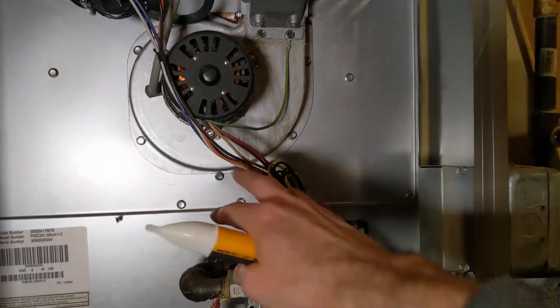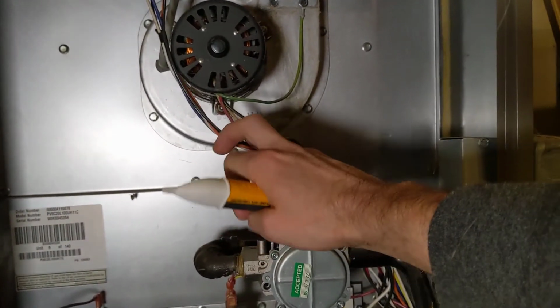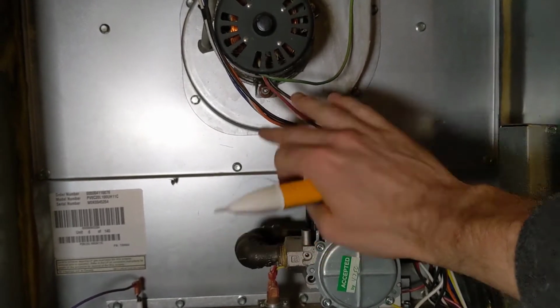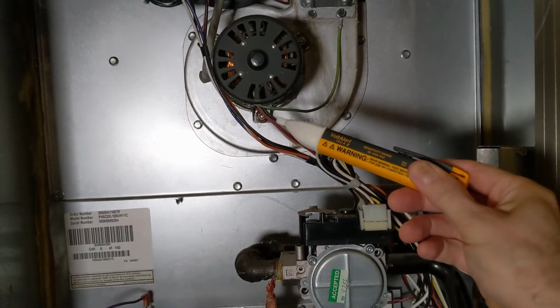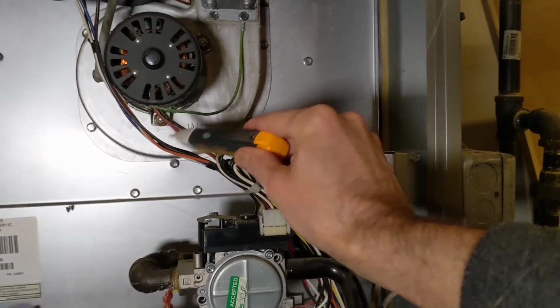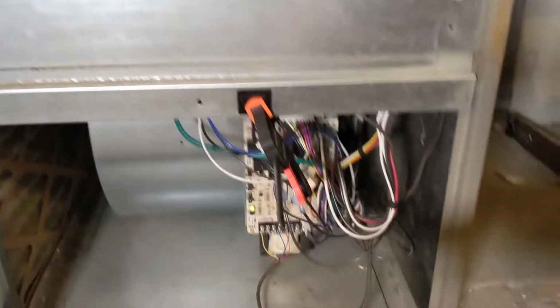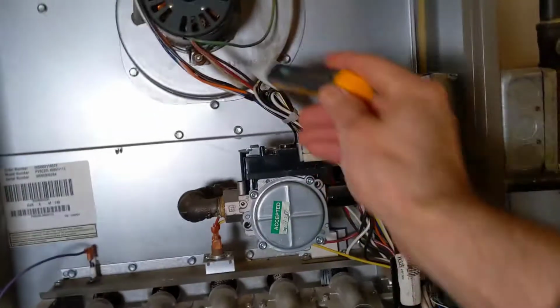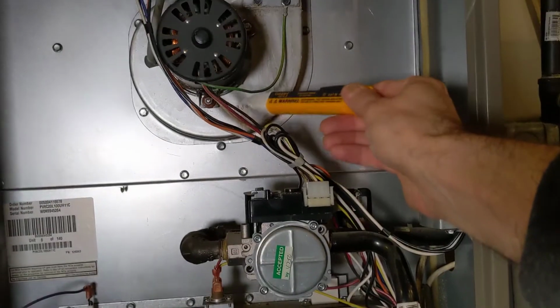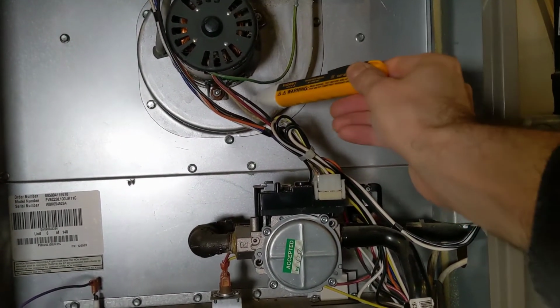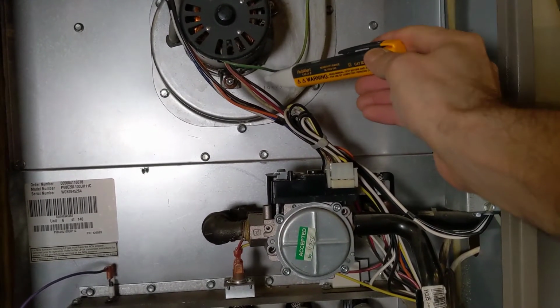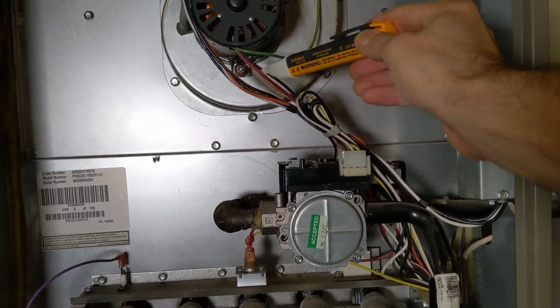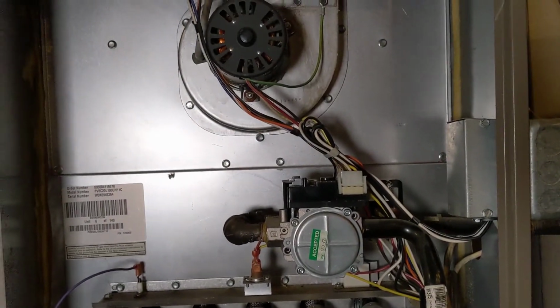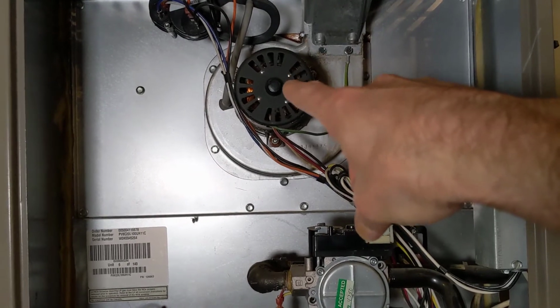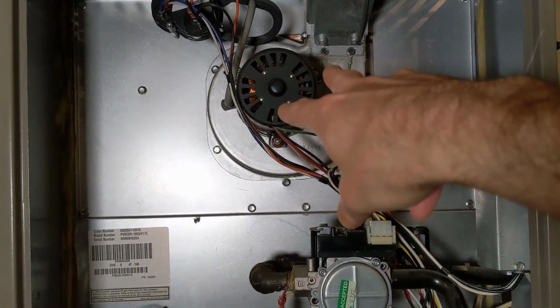The way you can maybe make a determination of that is this motor has some wires coming into it, usually like a red, white, or red, white, and black. What I would do is take my non-contact voltage tester and see if there's any power going to these wires. If everything is lit up and it's calling for heat, you should have full line voltage, meaning 110 volts. That's typically what this motor runs at. So if you touch the black or red wire, I don't know which one it is, but it should light up your voltage detector. Now, if you have voltage and this thing still isn't running, it's likely that that motor went bad and that needs to be replaced.